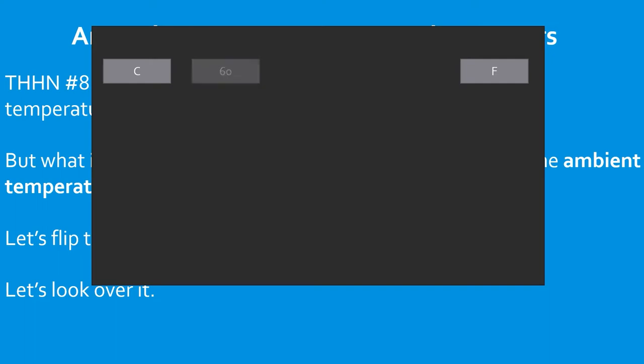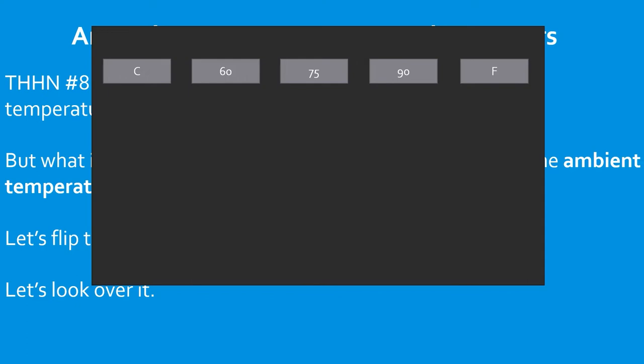Starting on the far left-hand side is the Celsius ambient temperature. If your question mentions the ambient temperature in Celsius, you select from the Celsius side. If it's Fahrenheit, you'll be on the far right-hand side. In the middle you'll have the 60, 75, and 90°C columns, which coincide with our primary ampacity table. Whichever column you selected your conductor from — 60, 75, or 90 — you'll use that same column here.